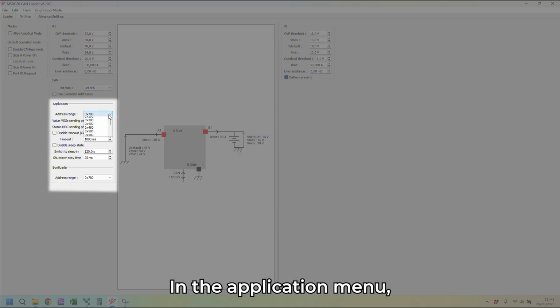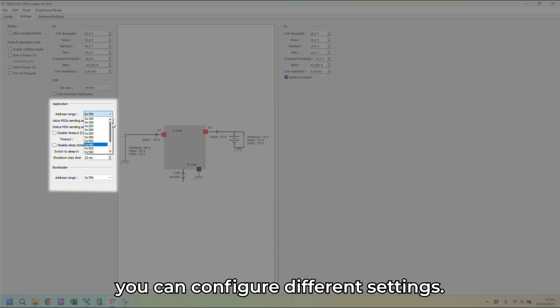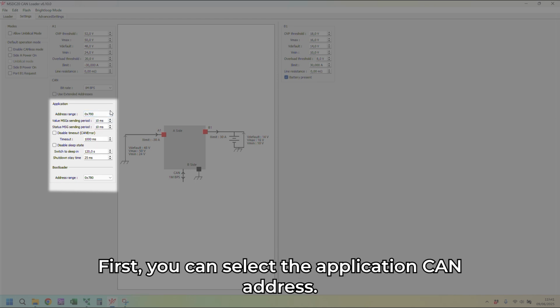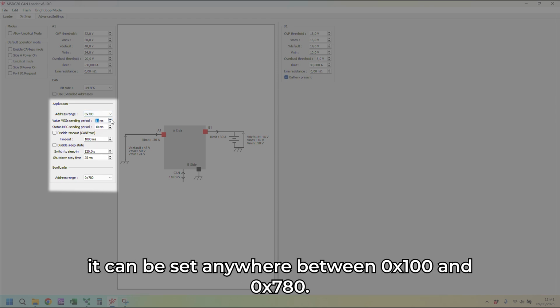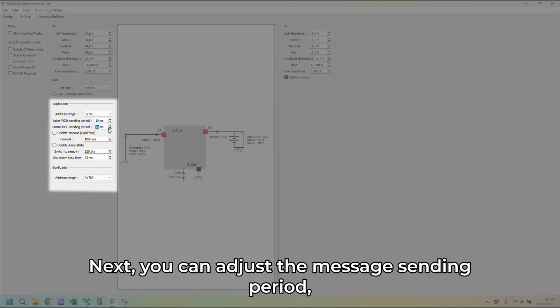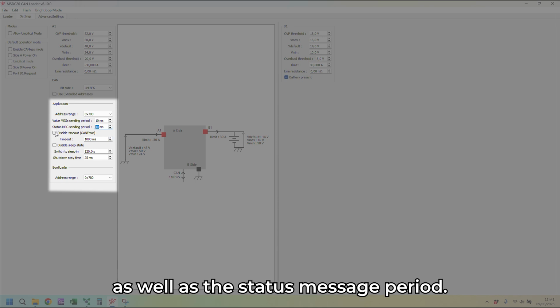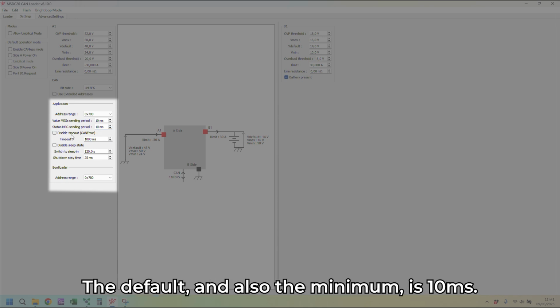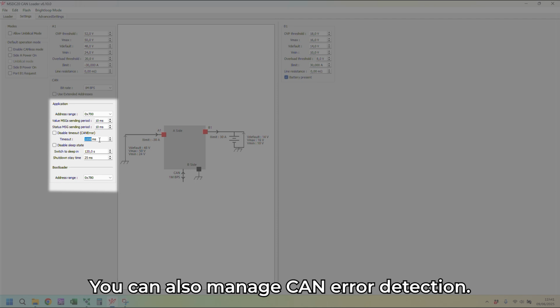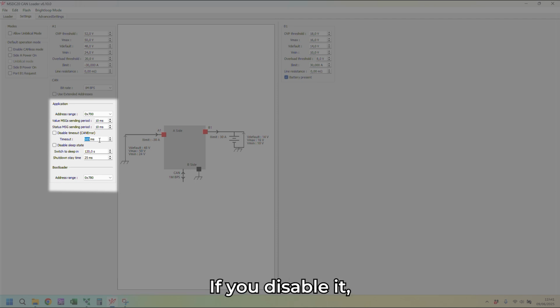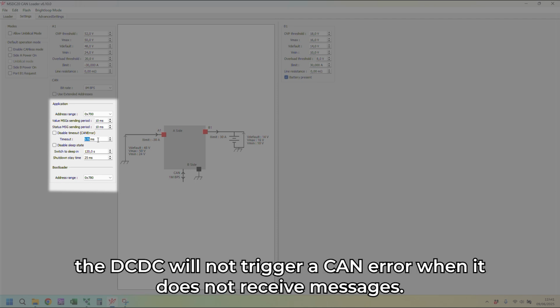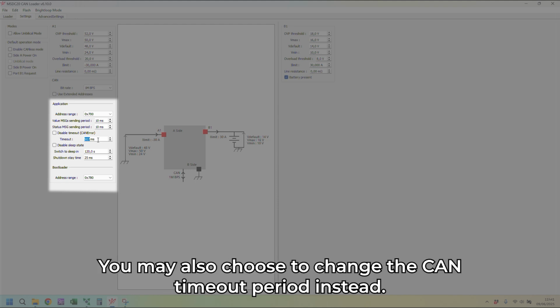In the application menu, you can configure different settings. First, you can select the application CAN address. It can be set anywhere between 0x100 and 0x780. Next, you can adjust the message sending period as well as the status message period. The default and also the minimum is 10 milliseconds. You can also manage CAN error detection. If you disable it, the converter will not trigger a CAN error when it does not receive messages. You may also choose to change the CAN timeout period instead.